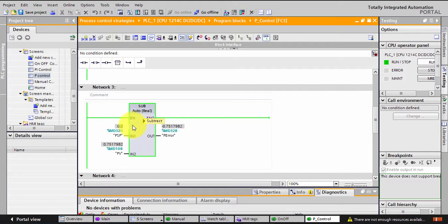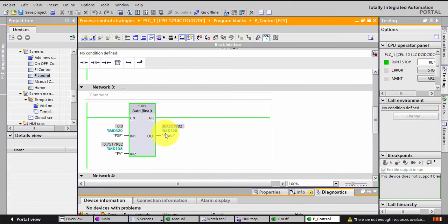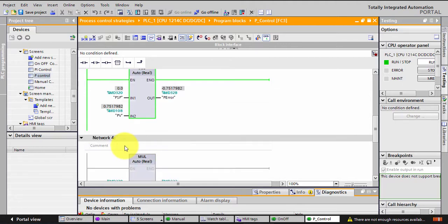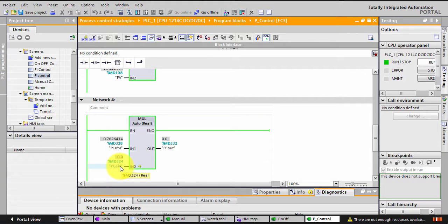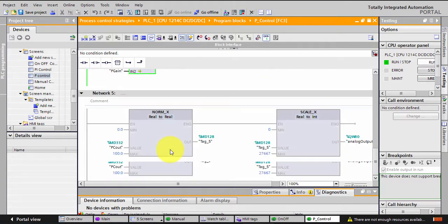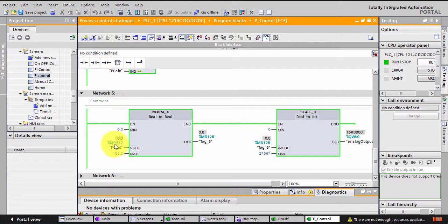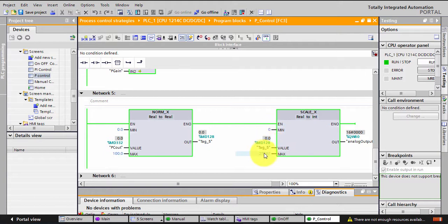What I'm doing here is the set point minus the PV, so I'm calculating the error. Remember the error is always set point minus PV. And now I'm multiplying this by the P gain. This is how the P control is done, multiplying the error by a gain. And I'm having my P out, and I'm changing this P out from zero to a hundred percent. The value I'll get, I'll put it from zero to 27,000 and give it to QW 80.